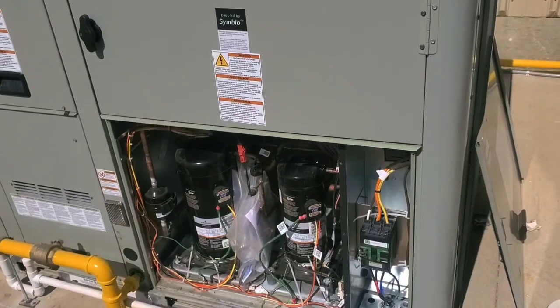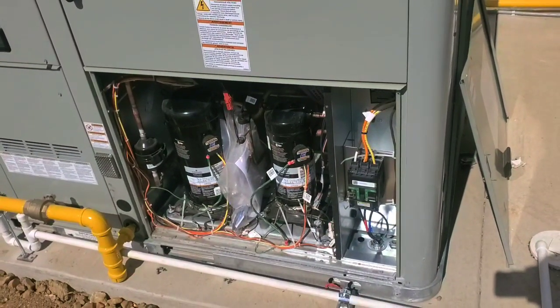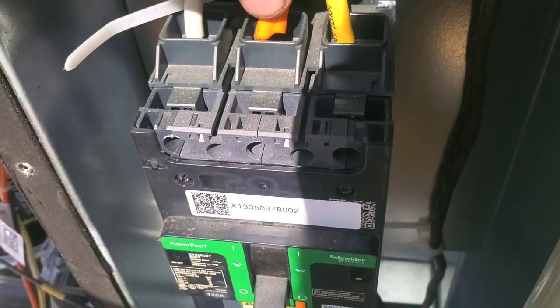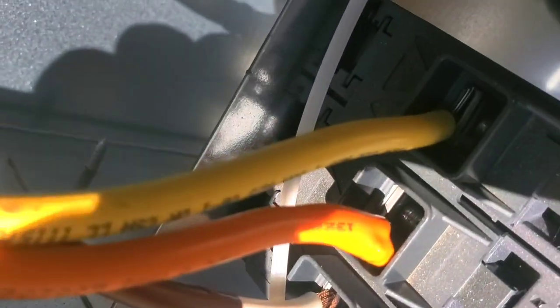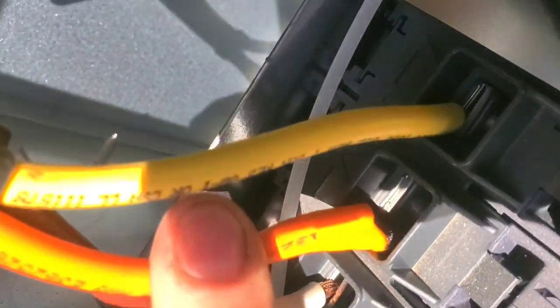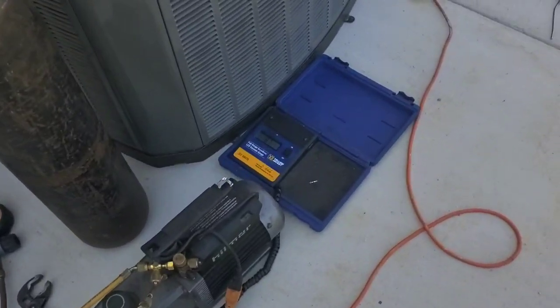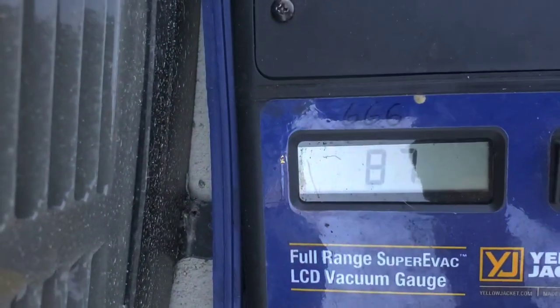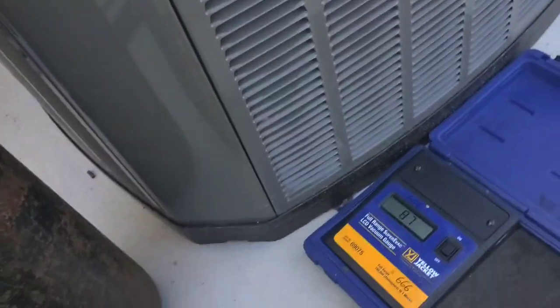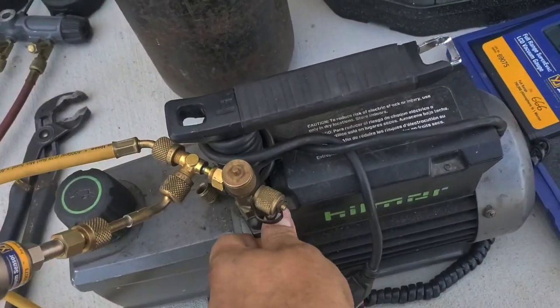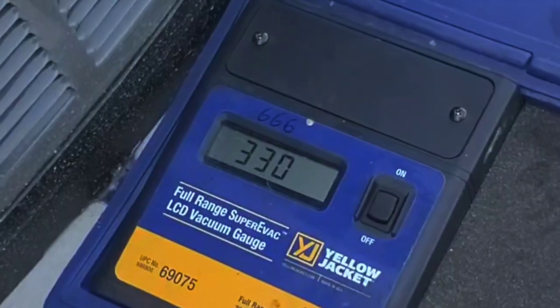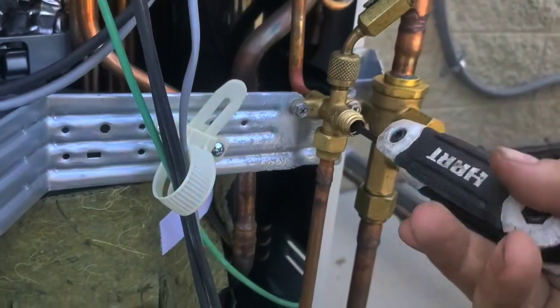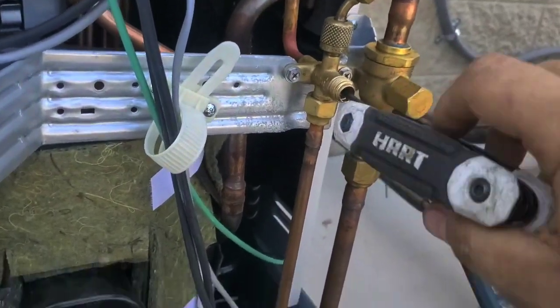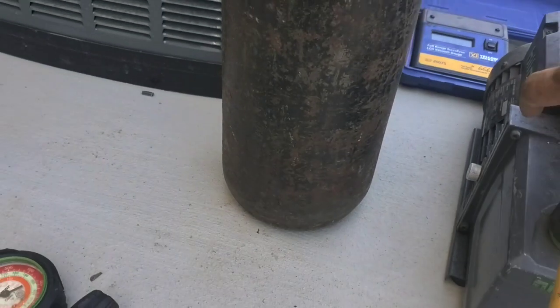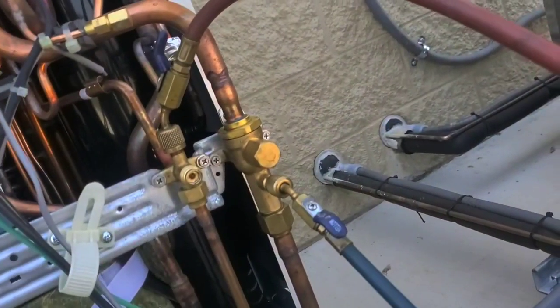This unit has been operating for a total of about 6 hours. This is the way it came from the factory. Really, I mean, you can see right over there behind this wire is the place where it's supposed to be screwed down. That's been a few hours. And we're sitting at 87 microns. What's it stay at if I close the valve on the vacuum tank? So that would be done.